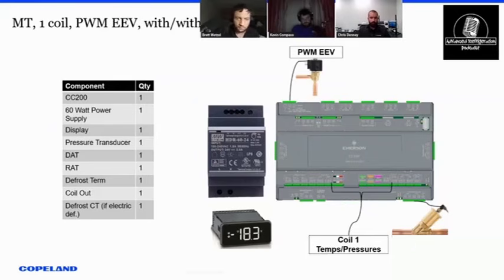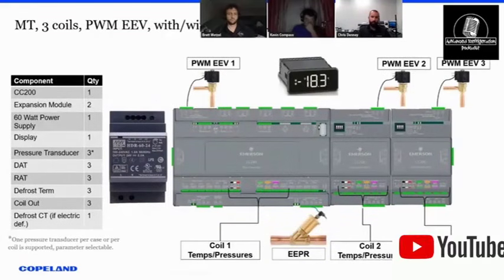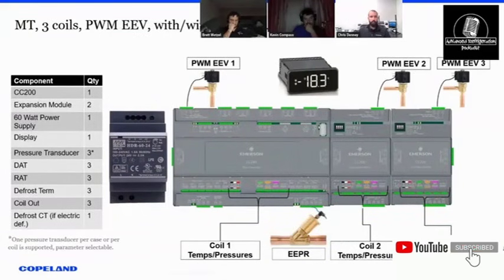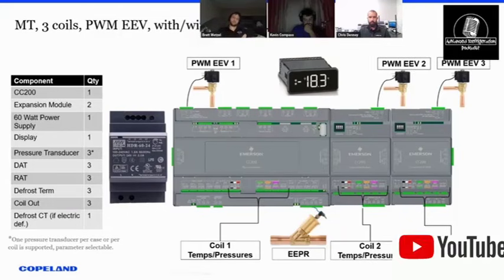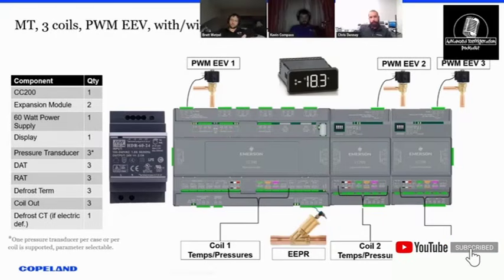I'm going to skip over this one because we covered it earlier and show you the multiple valve layout. So here we have a main controller and 2 expanders. This will be a 3-coil setup where you have pulse valve along the pulse valve connectors, main module, expander. And then optionally, if the customer wants the EPR, you throw that on the main controller. And then, of course, all your temps and inputs go along the bottom. If we're just doing 1 coil, the stuff on the right goes away, and we would just keep the main module.